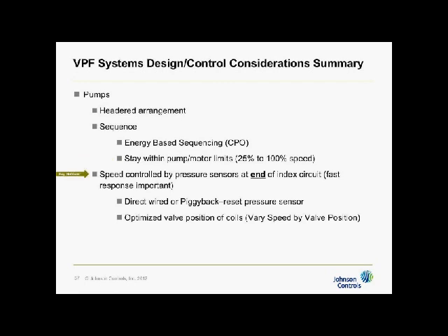Speed should be controlled by 2 possible methods. One was pressure and the other is valve position. With pressure, we want to make sure we do not locate the pressure sensor in the plant ever, not to control ultimately the speed forever. There's a way in which you can do it from the plant, but I'll explain that in a minute. We want to have it not 2/3 of the way down the system. We want it all the way to the end of the system. So you want to be on the index circuit as far as you can possibly be, near the longest run or the most resistive run all the way out through the index circuit. If you have a wandering index circuit, then put in more than 1 pressure sensor and choose the highest.